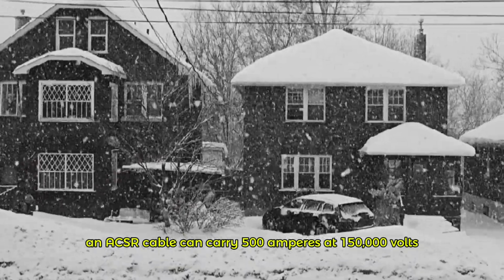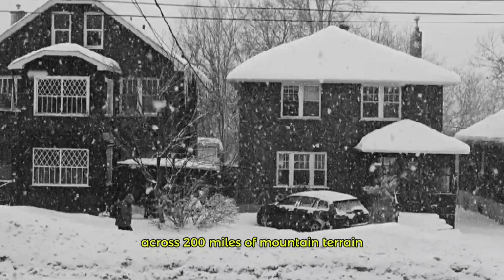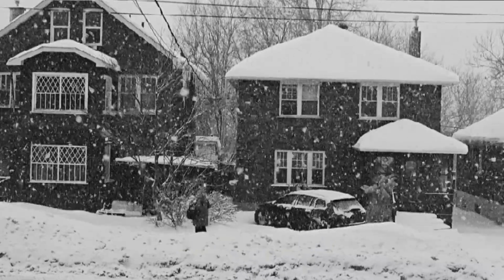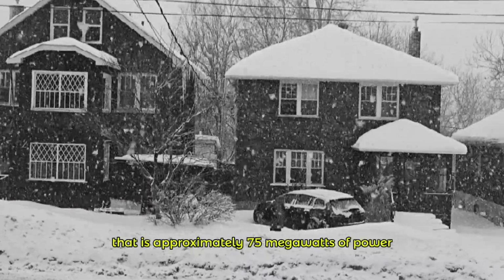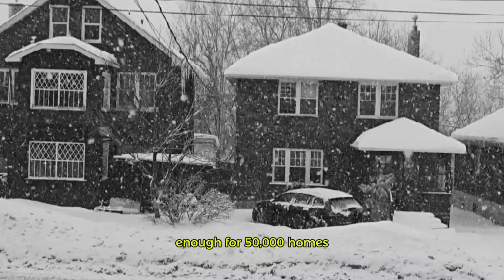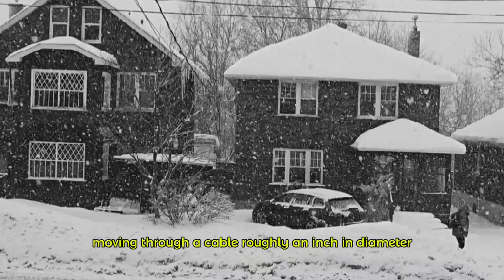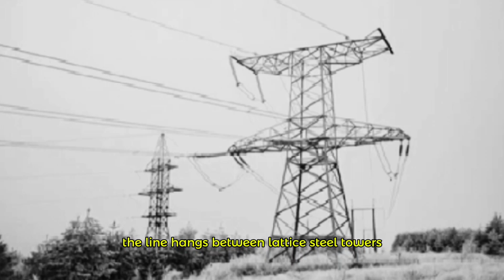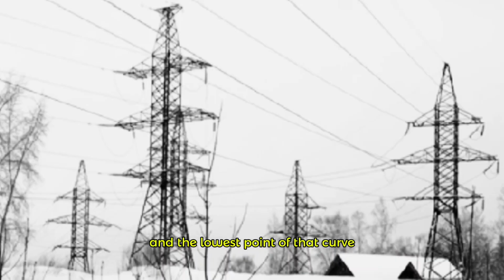without the other. Together, an ACSR cable can carry 500 amperes at 150,000 volts across 200 miles of mountain terrain with line losses under 3%. That is approximately 75 megawatts of power, enough for 50,000 homes, moving through a cable roughly an inch in diameter. The line hangs between lattice steel towers 80 to 120 feet tall. Between towers, the conductor hangs in a catenary curve, and the lowest point of that curve, the midspan sag, is engineered to maintain at least 25 feet of ground clearance at the highest expected conductor temperature.